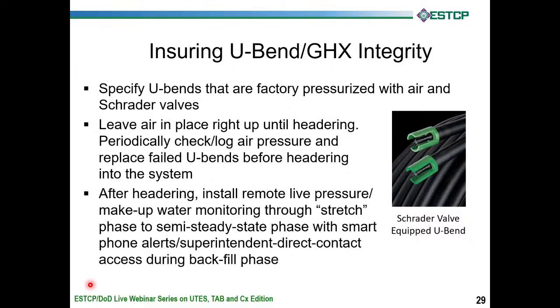You hook basically a pressure gauge, like you'd use on the tires of your vehicle, up to that and see if there's still pressure in there. If there's not, then you pump it up and see if it holds, and whether somebody just let the air out or it's got a leak, and you cut the leaking section of the pipe out or replace the U-bend before it ever gets anywhere near the ground. And then after those are inserted into the ground, we like to leave those two ends sticking up 3 or 4 feet above the ground and come back periodically and check the pressures in there to make sure they haven't fallen off. Either the commissioning agent or the contractor makes a log of each of those and testifies that all the U-bends are still good. And then we header everything together.